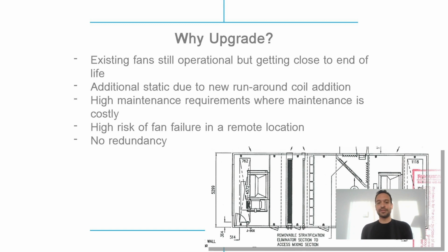They were going to upgrade their energy recovery runaround coils as well. So they were going to add a little bit of static to their coils and to their system. And that was another reason to upgrade the fans. The fans were pretty close to their high static, so they didn't want to use these fans. And as I said, the maintenance requirements were going up. There was a high risk of failure in a remote location, and they had no redundancy. So that was the main reason to just avoid a failure of these fans.